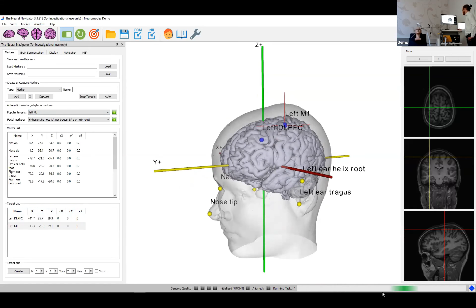So we'll start the tracker. This is simply initialization of the electronics. And whenever it's finished, it will ask us to capture the first marker as part of the set. In the bottom left, you can see that the software asks us to capture the nasion, and that's also highlighted in the 3D image. So Shows will point with the pointer at the nasion, and then using the remote control, you can capture that position. And we hear an auditory confirmation that this has been done.